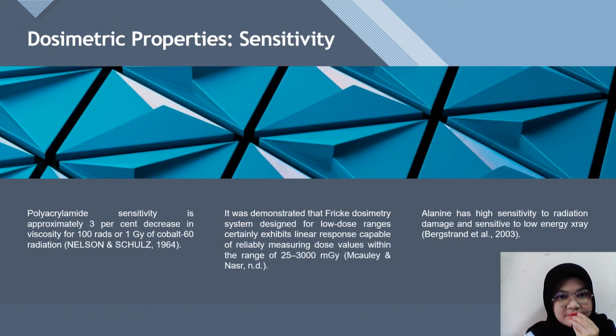So the next property is sensitivity, which is the sensitivity of the polyacrylamide, Fricke dosimetry, and alanine dosimetry. The first one, from Nelson and Schulz 1964, said that polyacrylamide has a sensitivity of approximately 3% decrease in viscosity for 100 rad, or 1 gray, of cobalt 60 radiation.